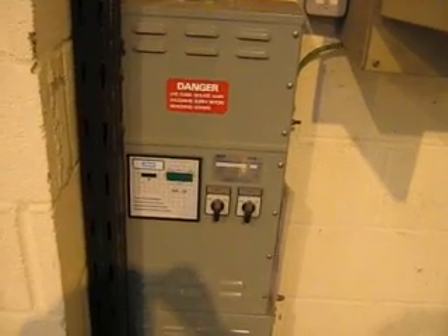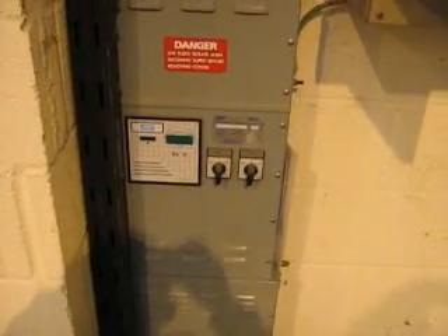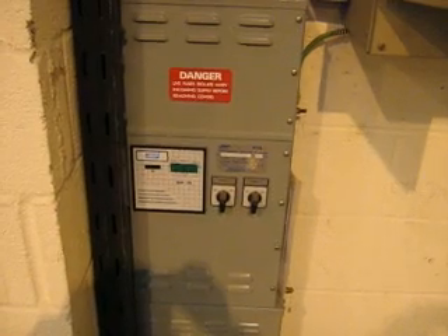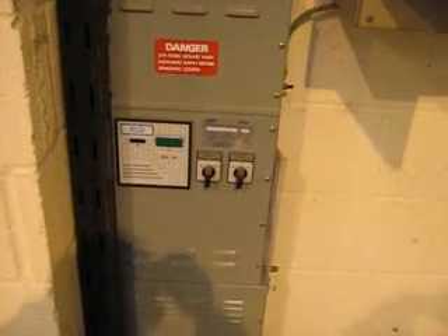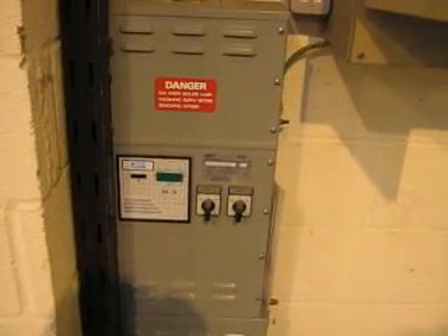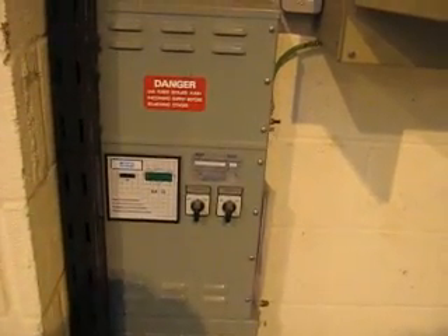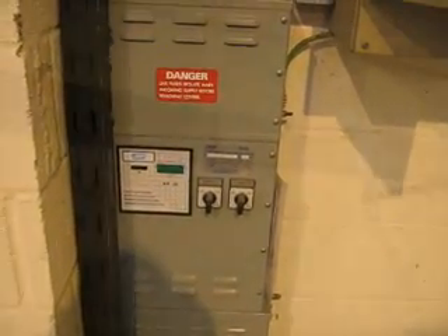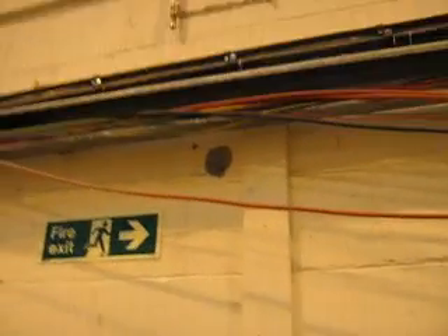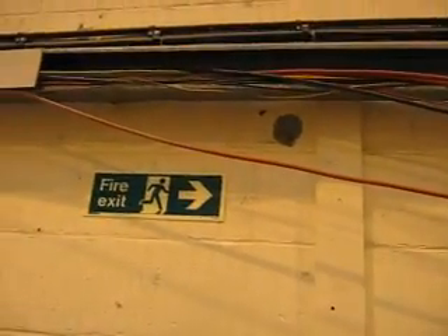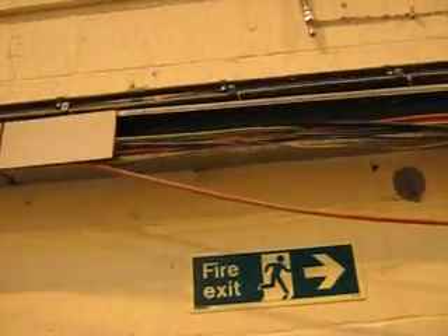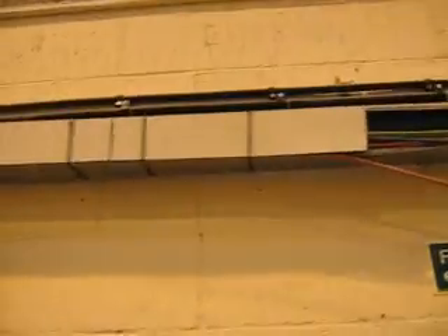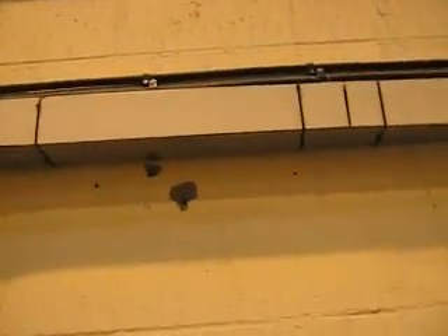Just here is power factor correction equipment. It appears to be switched off or disconnected. Damaged trunking, and also the lid missing, which is very common in this place. Mineral insulated cables hanging down. Something must be done about that. Somebody's stuck some hardboard up there. Is there a trunking lid?